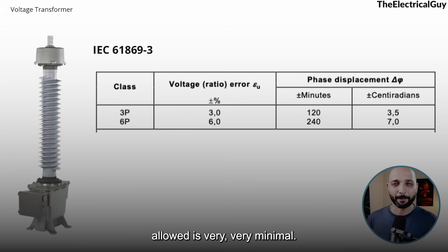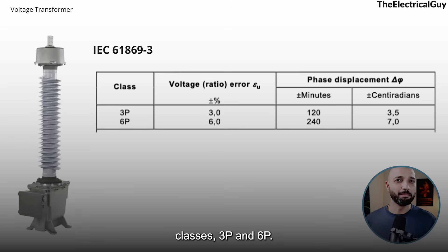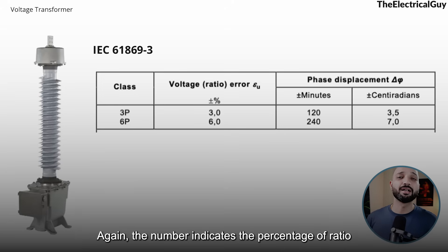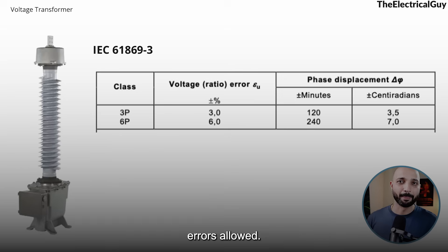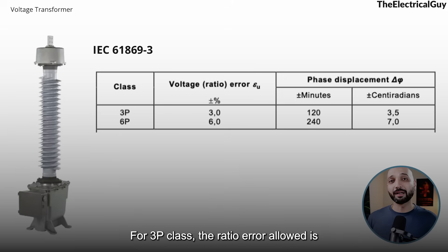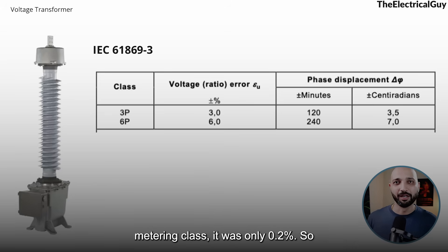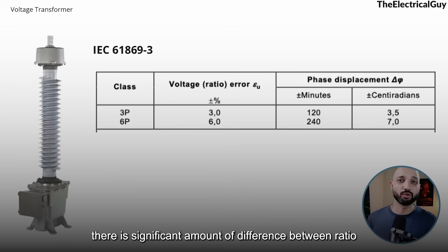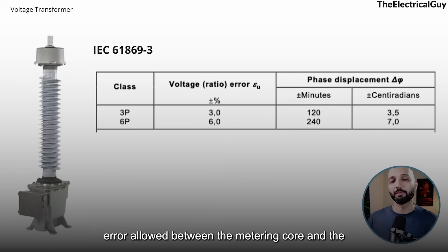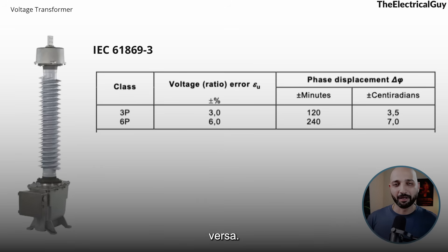Similarly, for protection purposes IEC has defined two classes: 3P and 6P. Again, the number indicates the percentage of ratio error allowed. Here is the example table from IEC — for the 3P class the ratio error allowed is 3%. Compare that with the 0.2 metering class where it was only 0.2%. There is a significant difference in the ratio error allowed between the metering core and the protection core, which is why you should not use a protection core for metering or vice versa. The phase displacement values are also given for the 3P and 6P classes.